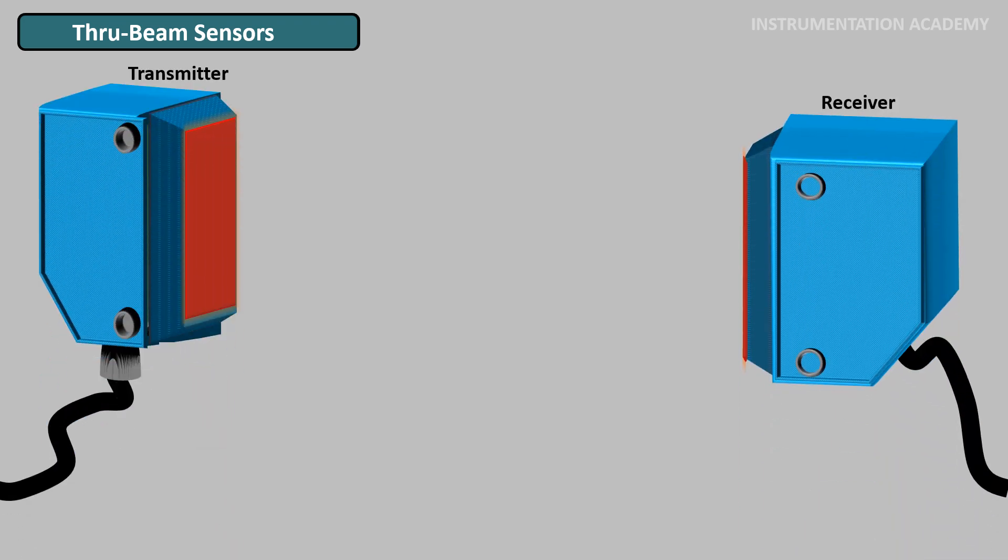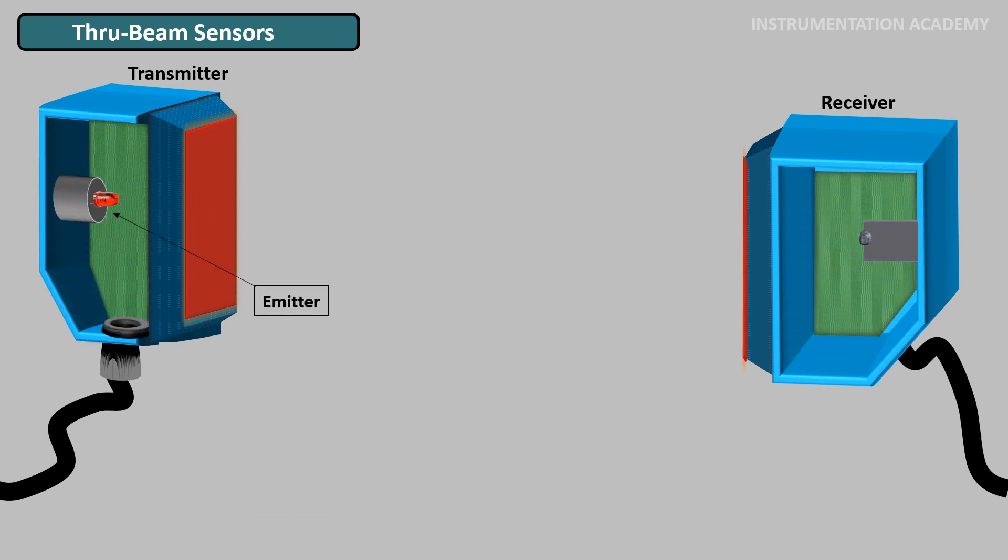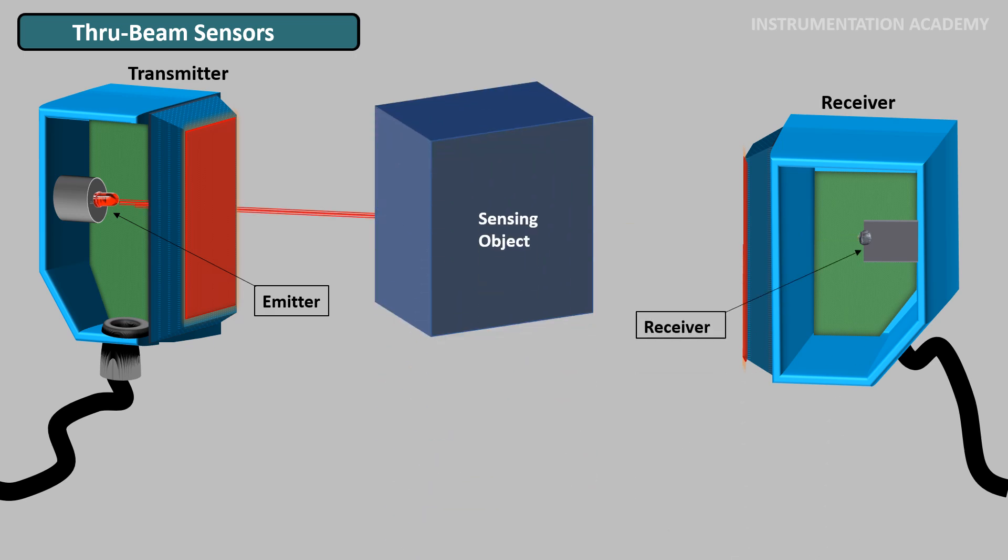Through beam sensors are photoelectric sensors with a separate transmitter and receiver which are placed facing each other. This is also called a through beam configuration. In this type, an emitter sends out a beam of light directly in the line of sight of the emitter to a receiver. When an object breaks this beam of light, it reduces the amount of light that enters the receiver. This reduction in light intensity is used to detect an object.